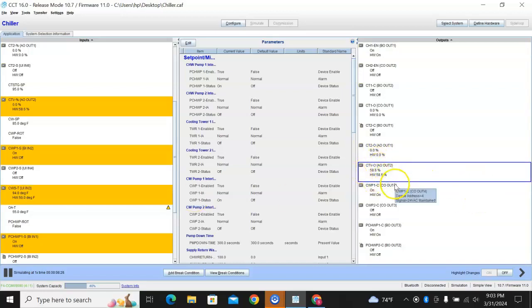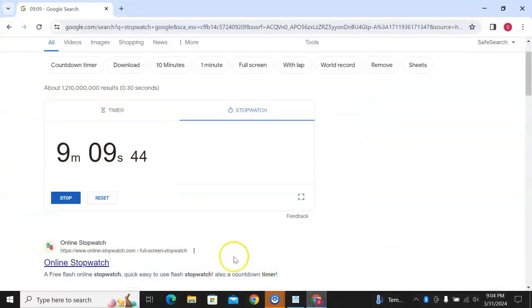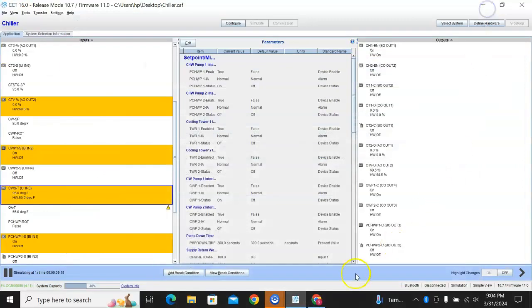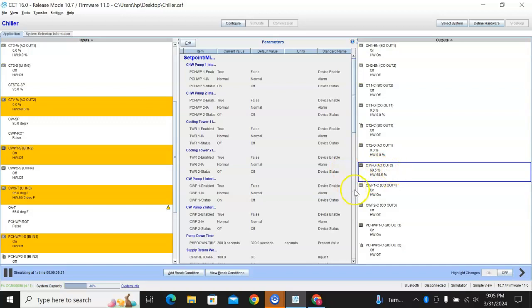Still not 100% over the top. Add another degree, 95. Now, full 10 degrees over, 9 minutes. 68% over the tower. So we're still bypassing 32% of the water.